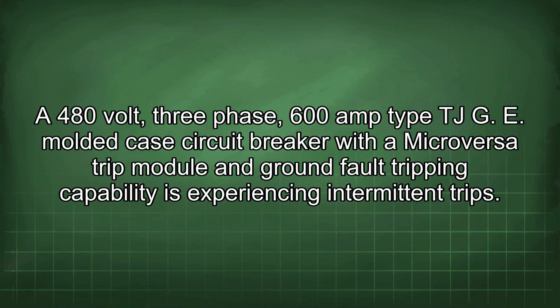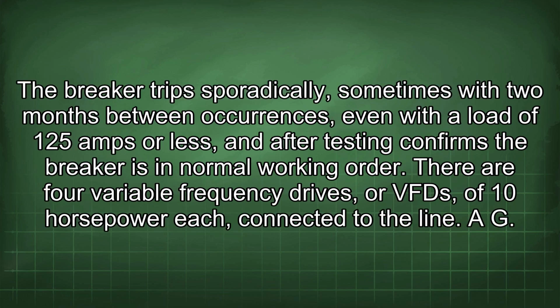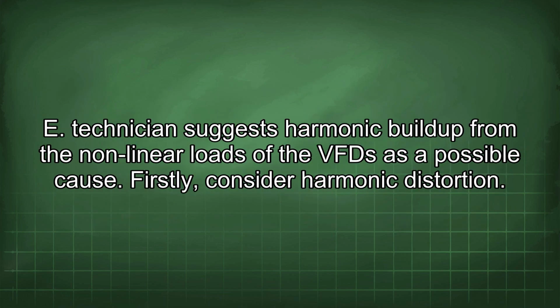A 480 volt, 3-phase, 600 amp type TJGE molded case circuit breaker with a Microversa trip module and ground fault tripping capability is experiencing intermittent trips. The breaker trips sporadically, sometimes with 2 months between occurrences, even with a load of 125 amps or less, and after testing confirms the breaker is in normal working order. There are 4 variable frequency drives, or VFDs, of 10 horsepower each connected to the line. A GE technician suggests harmonic buildup from the nonlinear loads of the VFD is a possible cause.